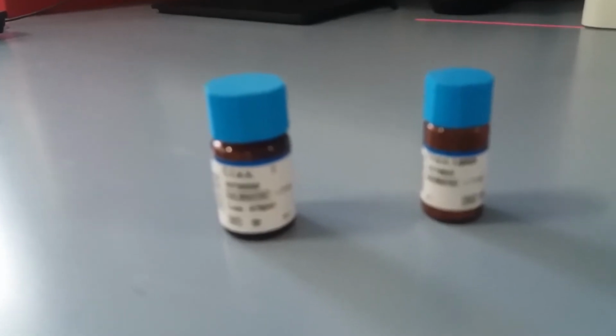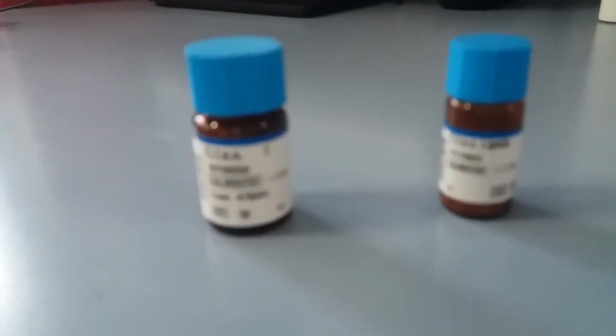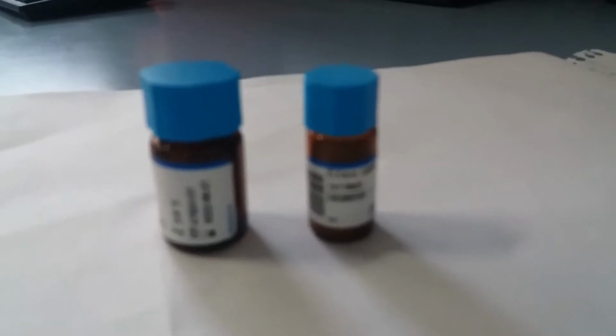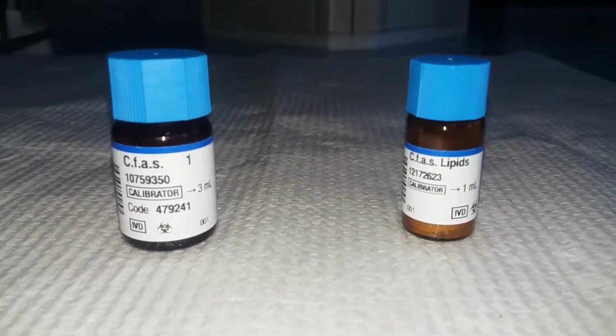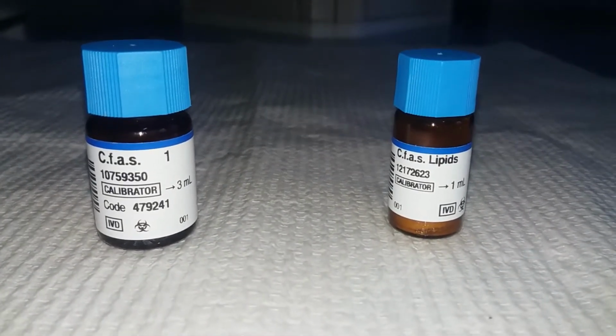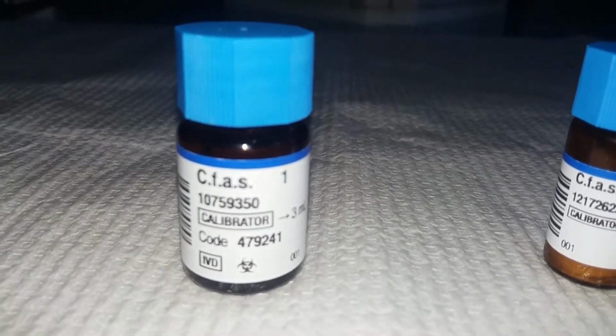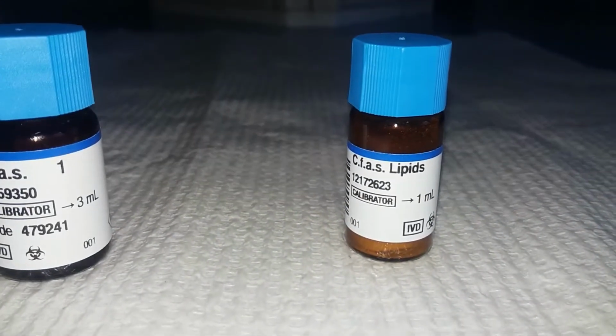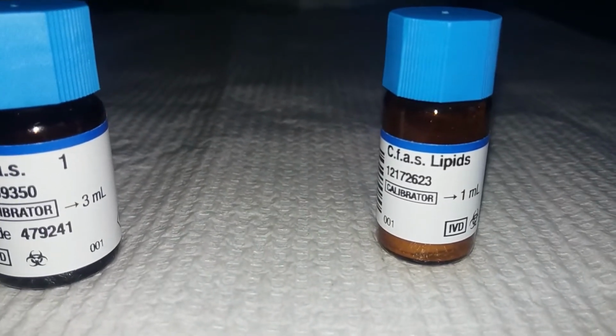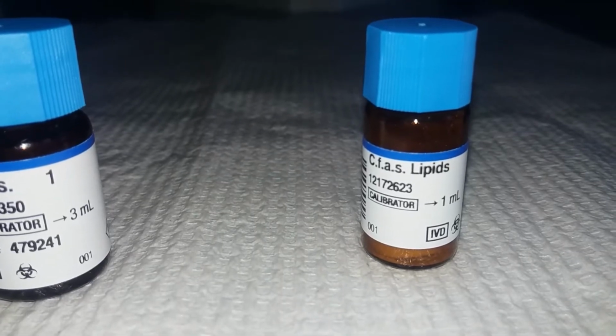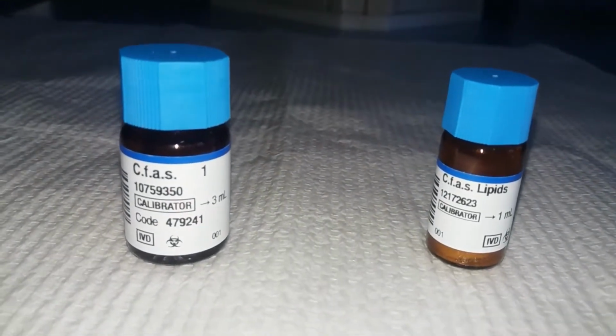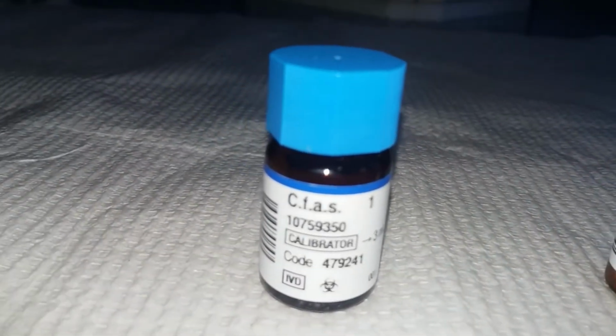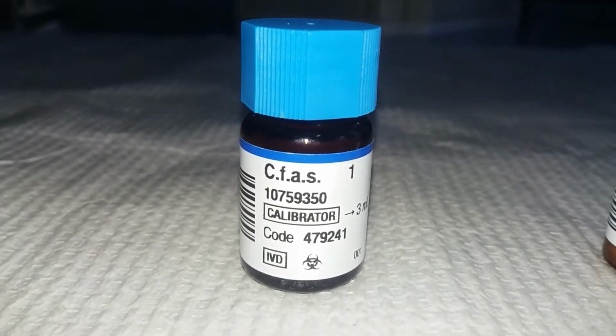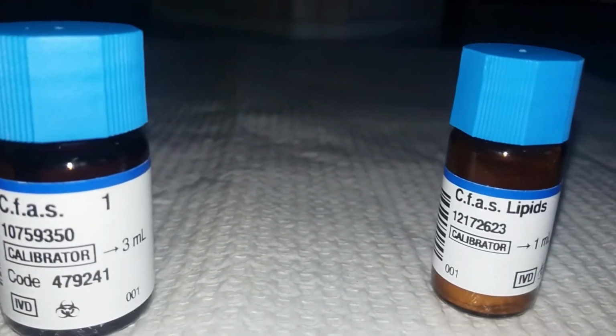When we come to calibrator and quality control, both multi-calibrator and specific calibrator can be used for basic chemistry tests. Those calibrators are, for example, CFAS calibrator for automated systems, used to calibrate most of the clinical chemistry tests. This is one of the multi-calibrators. When we say specific calibrator, for example, CFAS CKMB is used to calibrate CKMB, CFAS Lipid for calibration of HDL and LDL, PreciControl fructosamine for calibration of fructosamine, and others can be used. For immunoassay, the calibrator used is a specific calibrator.